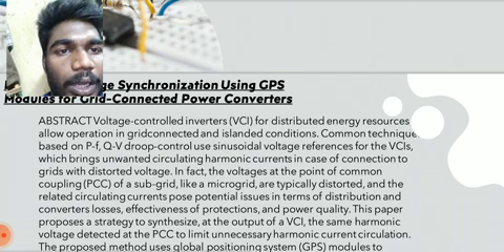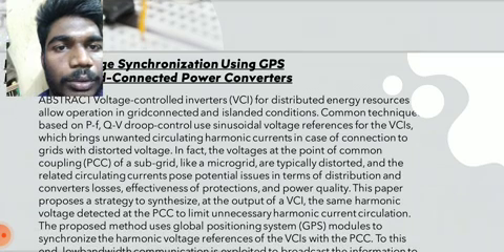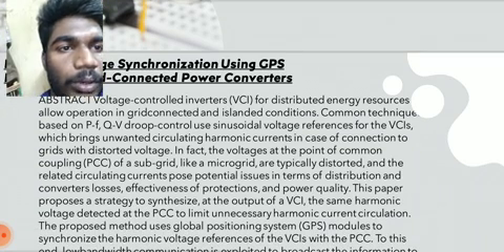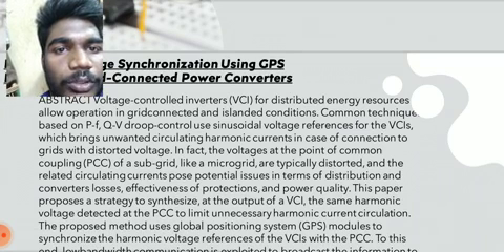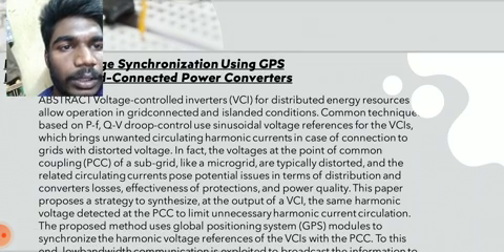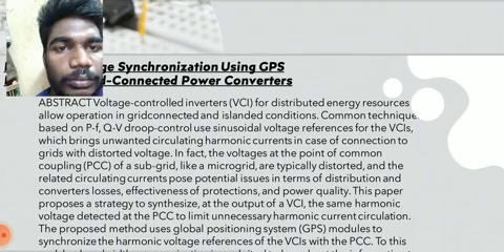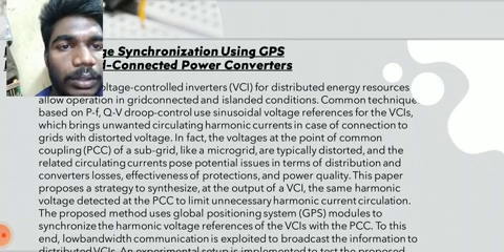Voltage controlled inverters, VCI, for distributed energy source allow the operation in grid connection and islanded condition. So the common technique based on the P-f and Q-V droop control using the sinusoidal voltage reference to the VCI brings unwanted circulating harmonic current in the case of connection to the grid with distorted voltage. In fact, the voltage at the point of common coupling, PCC, of subgrid like microgrid are typically distorted, and the related circulating current poses potential issue in terms of distribution and converter losses, effectiveness of the protection, and power quality.